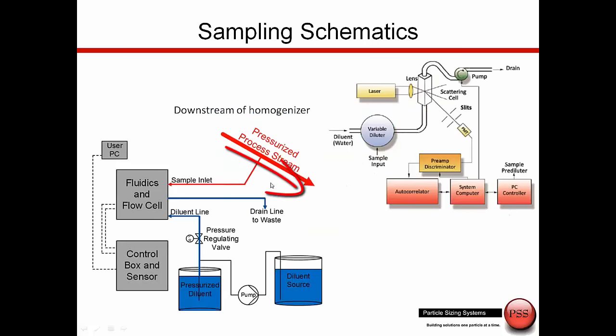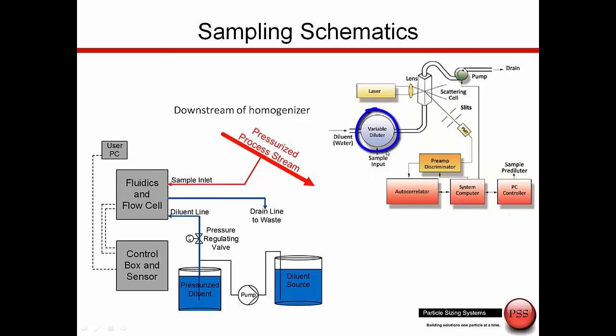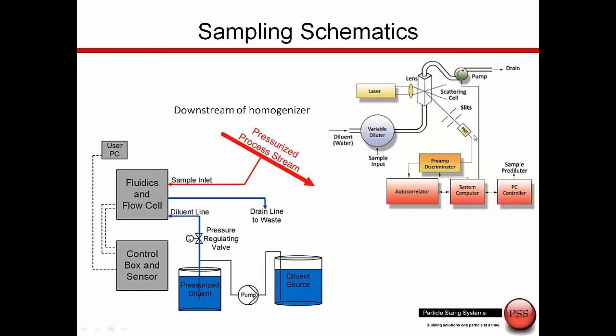Here the sample comes downstream of the homogenizer, into the fluidics, with the sample inlet and diluent inlet. The diluent is pressurized — it's best to have it pressurized so we can get very quick dilution. Sample comes in, diluent comes in, and this is where we do this automatic dilution. After performing this dilution, we bring the sample up to the measurement zone, where it becomes a standard DLS measurement: a light source, a detector, we get the correlation function and do our calculations. We get a result, then clean the cell and get ready for the next measurement.